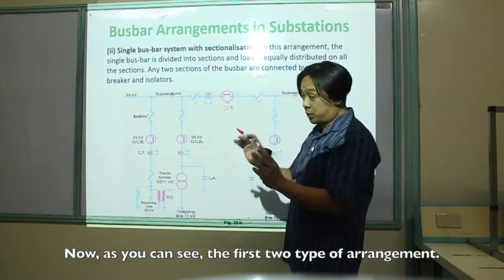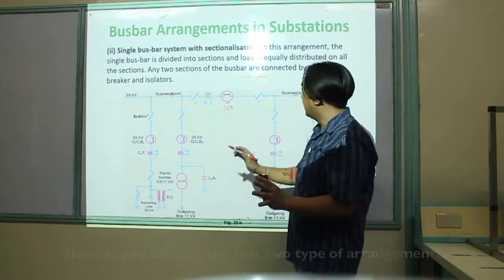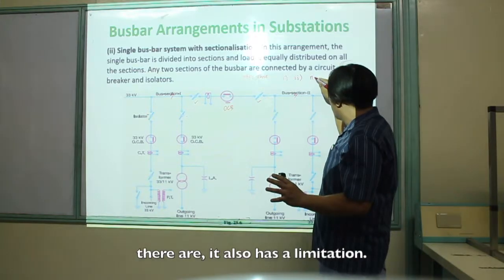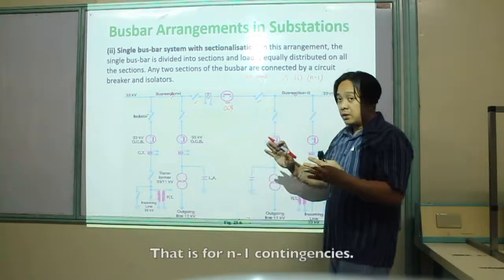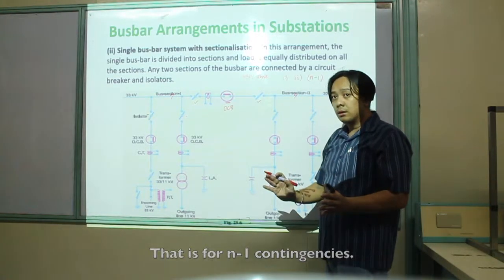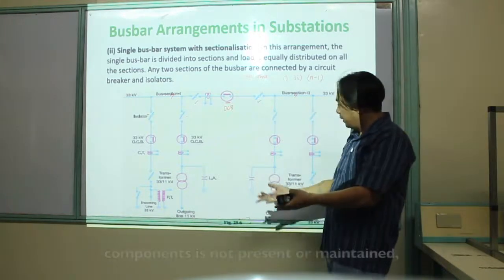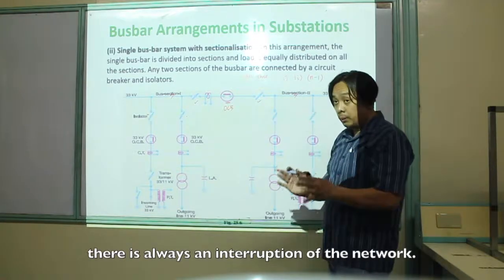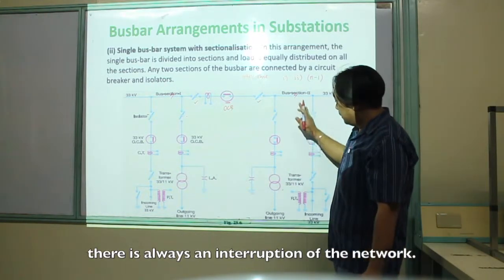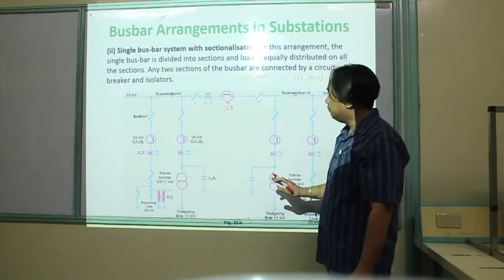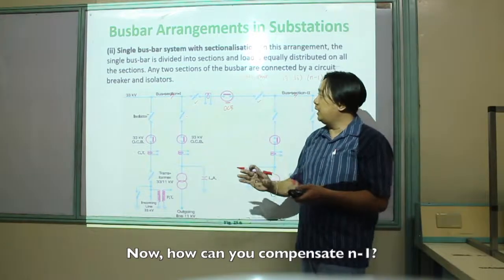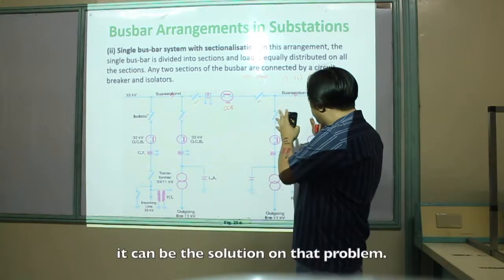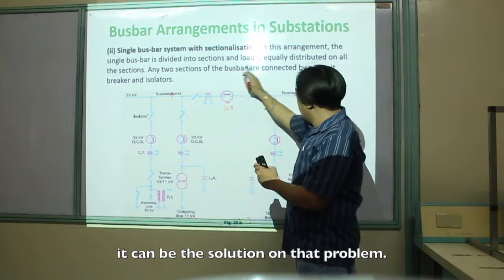The first two types of arrangement have a limitation — they are only for N-1 contingency. Meaning, if one of the bus bars or components is not present or being maintained, there is always an interruption of the network. The next few arrangements can be the solution to that problem.